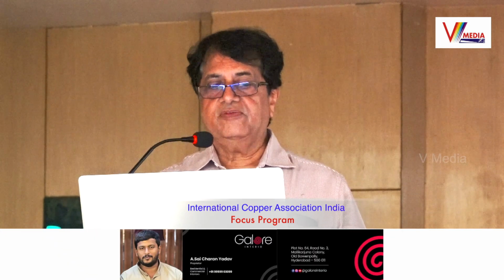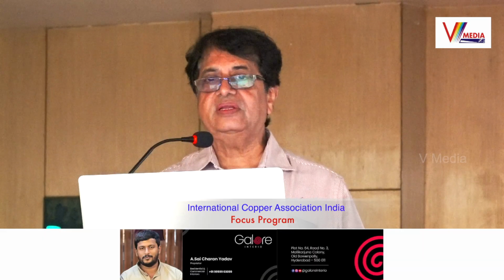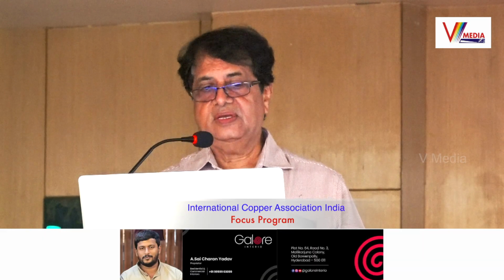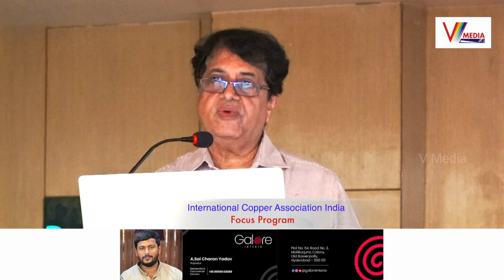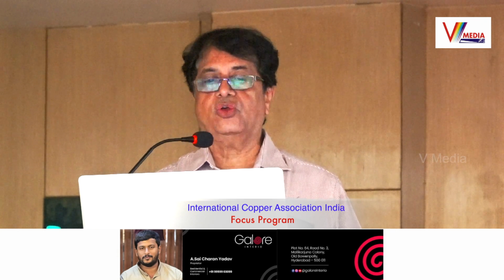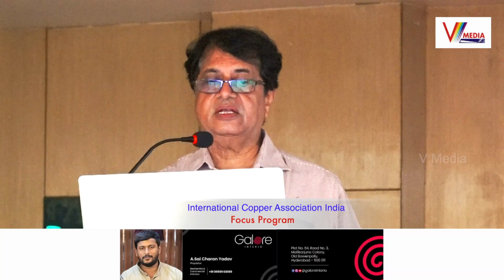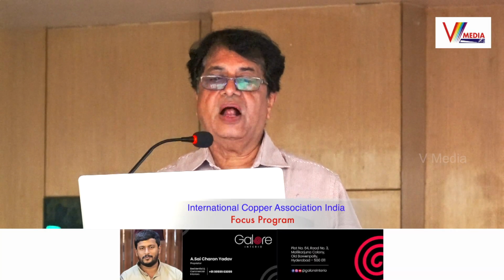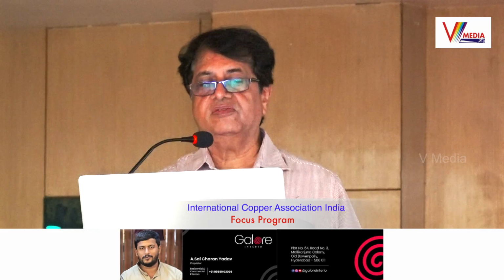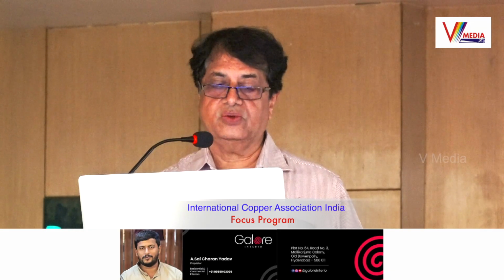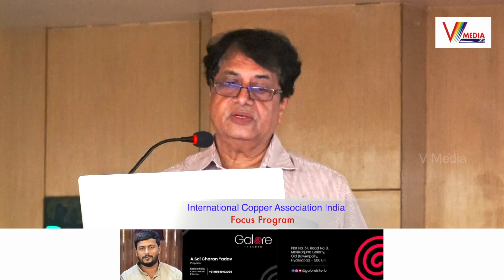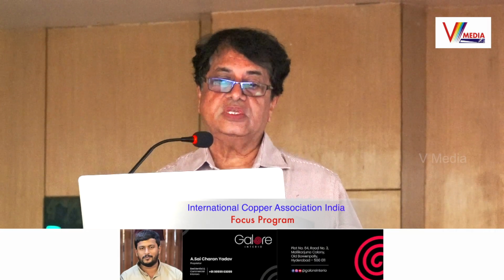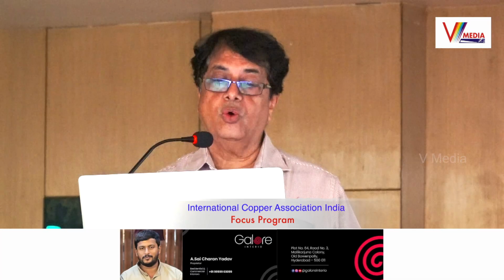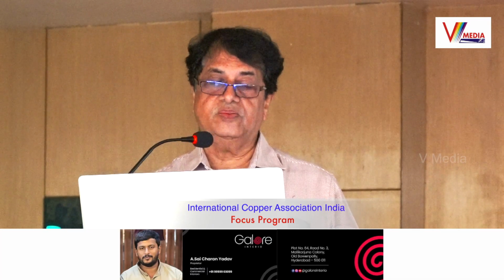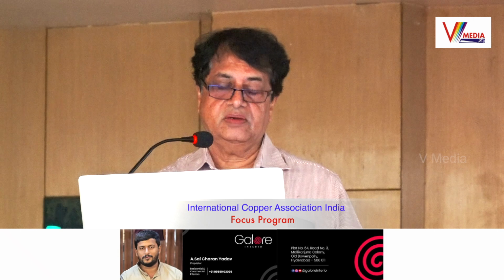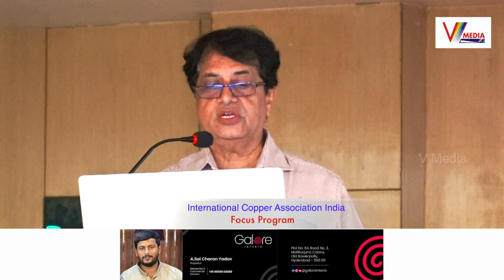The electrical meter room is again one of the very prime locations where an electrical fire begins. This fire may begin because of a fault of any occupant. If the system doesn't get tripped within his flat, then the fire may pass up to the meter room, and once one meter catches fire, it may engulf the whole meter room also. So there are different conditions mentioned in the code that you have to consider. That includes the clearances, the openings of the doors of the meter room, the ventilation system required within the meter room, and the location of the meter room.